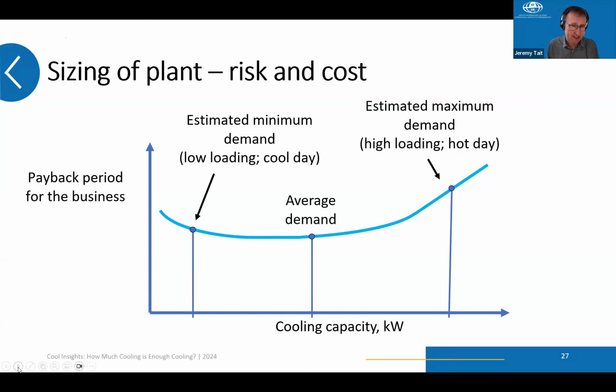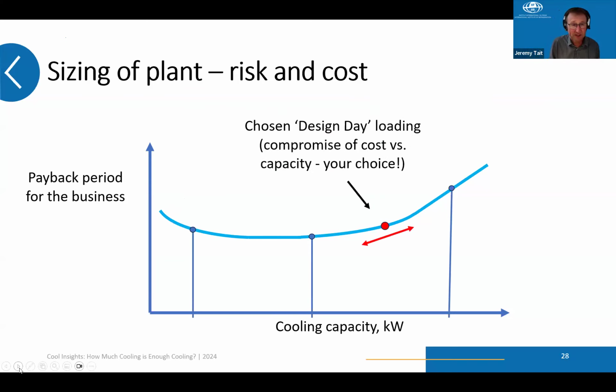You want to get some idea of where the minimum and maximum might be, some idea of the average, and you're going to want to choose a design day setting somewhere between the average and the peak. This is going to be your decision. You've got to make some sort of compromise, but you do need a decent idea of what your load might be to have plant that's able to do the job.